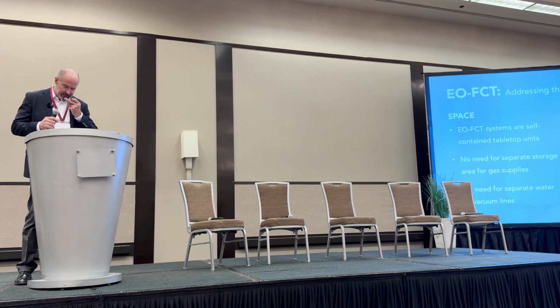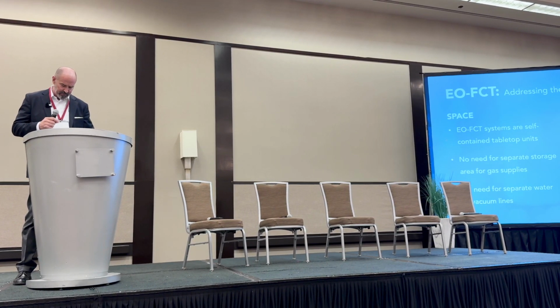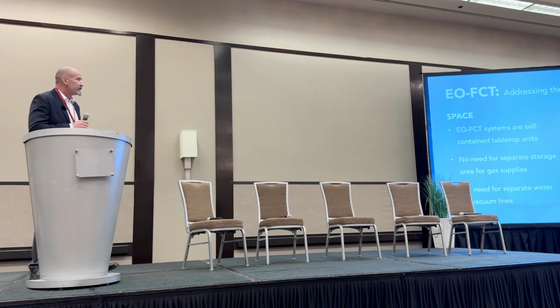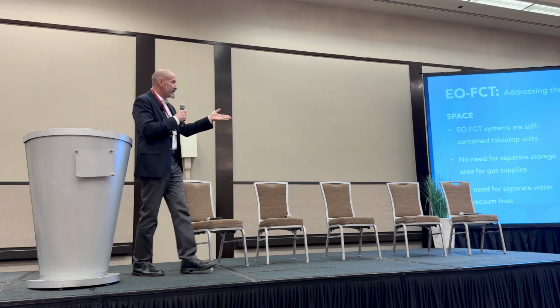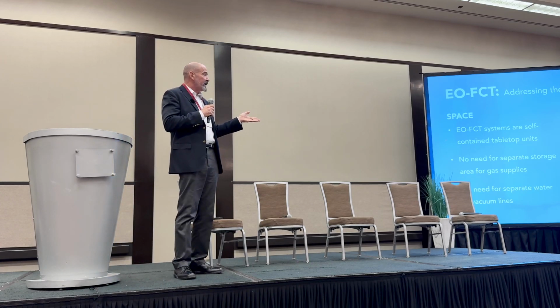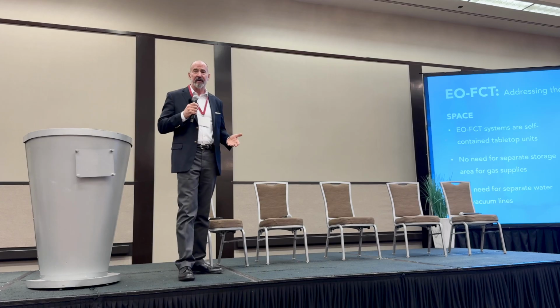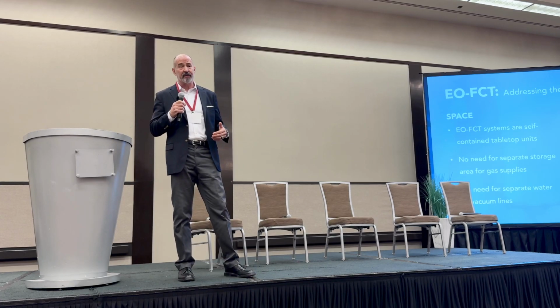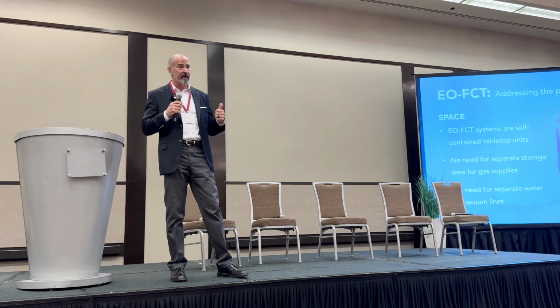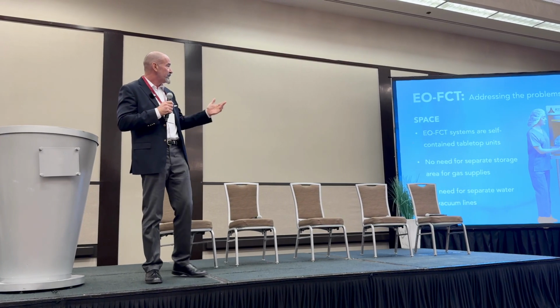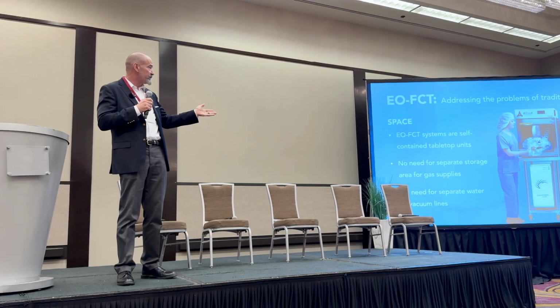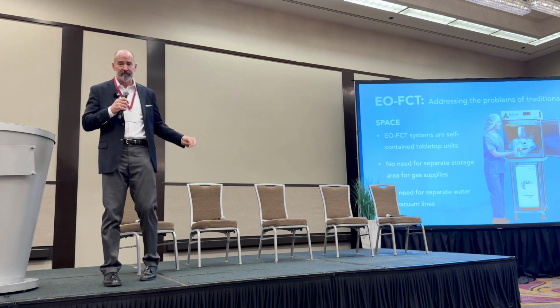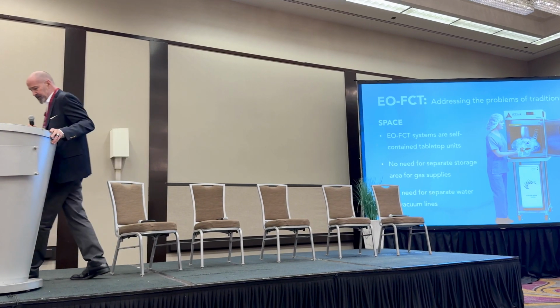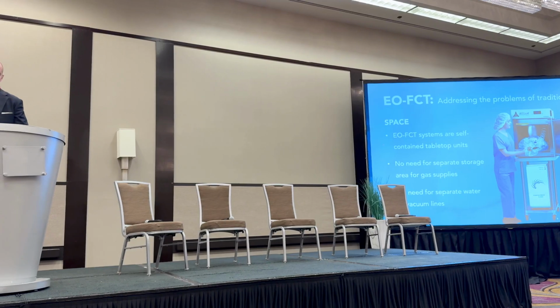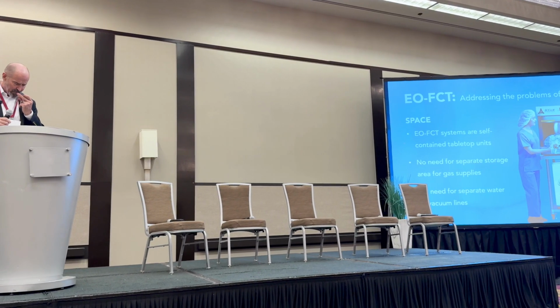In terms of space, again, this is a very, very different system. The system that we have cleared by FDA is a tabletop sterilizer. Very significantly, it's a self-contained system. Unlike earlier ethylene oxide systems, there are no water lines, there are no compressors. This is easy to set up, easy to install, easy to operate. It'll fit into pretty much any department at this point, taking up very little space.